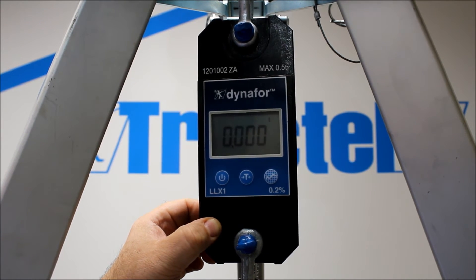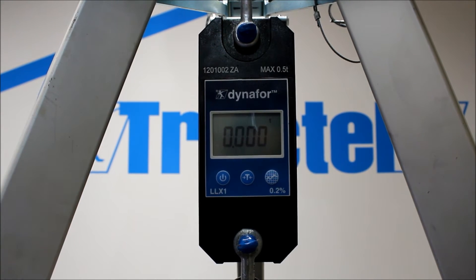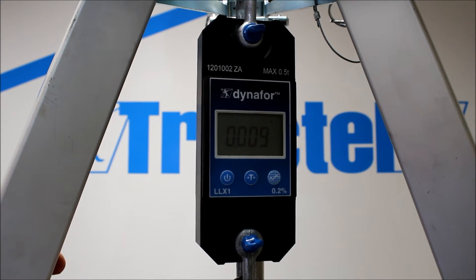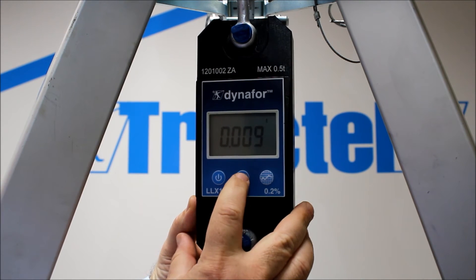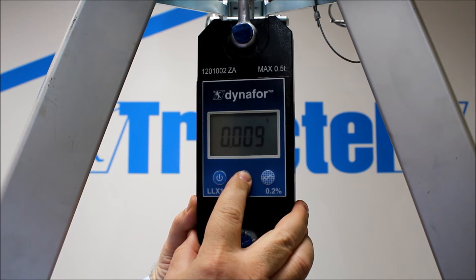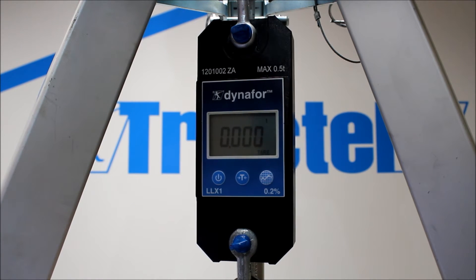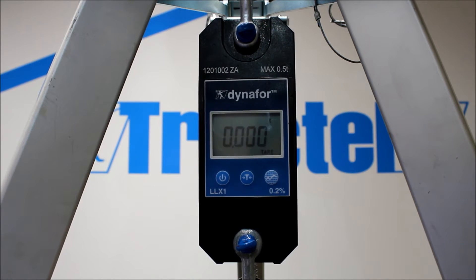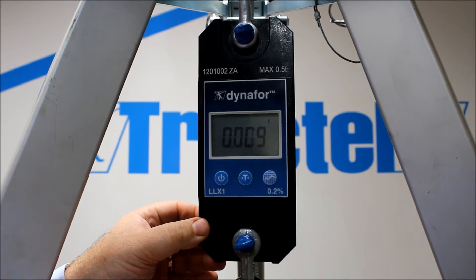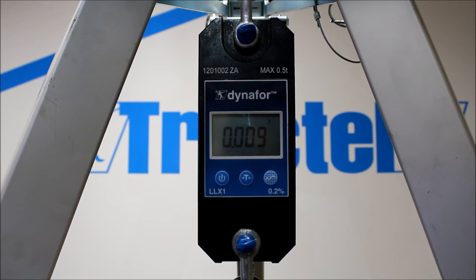We can also do a tare function, so we can suspend a load from the unit. It measures the weight of the mechanism, chain sling, or whatever it is that you're dangling on it. We can then press and hold down the tare function. The tare will come up and it will zero, so you can then see just the load that's applied. To take that off, a quick flick of the tare and the load's back there. Nice and simple — one two-finger operation.